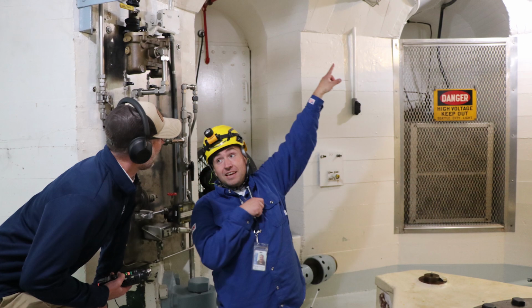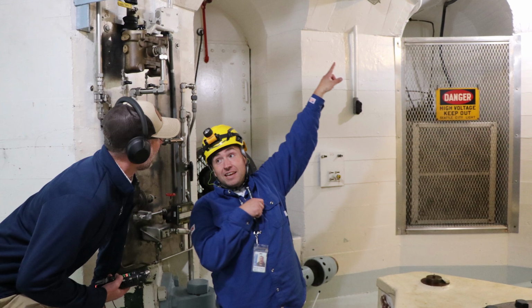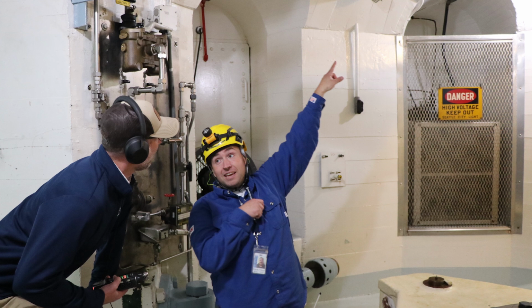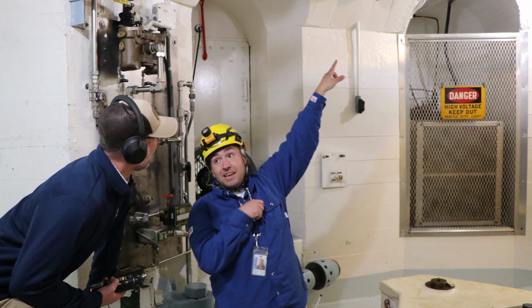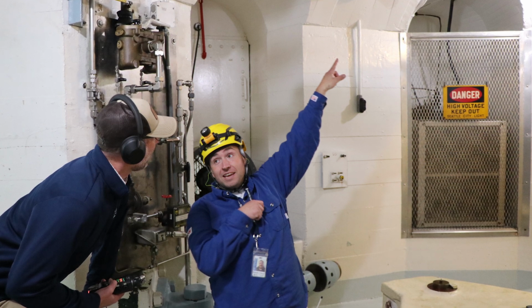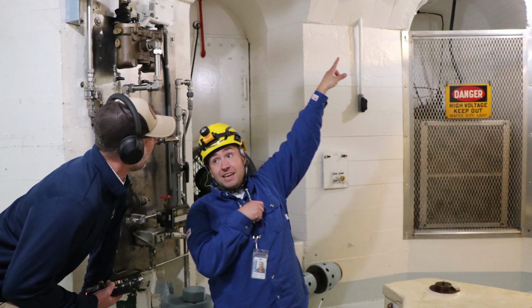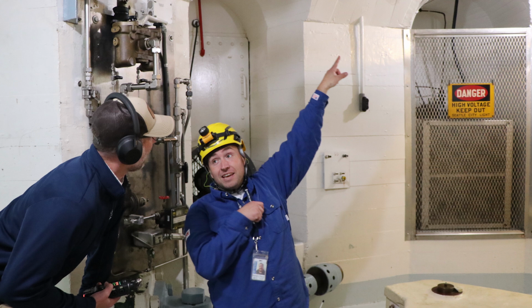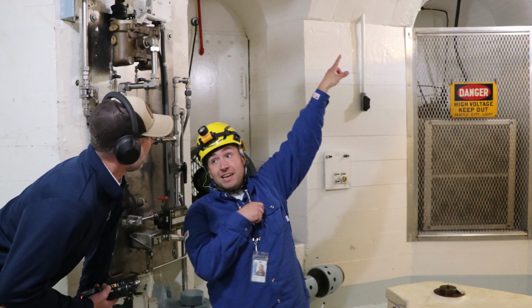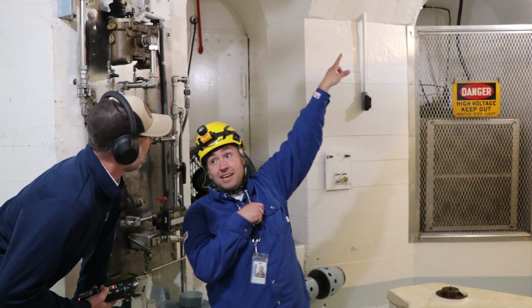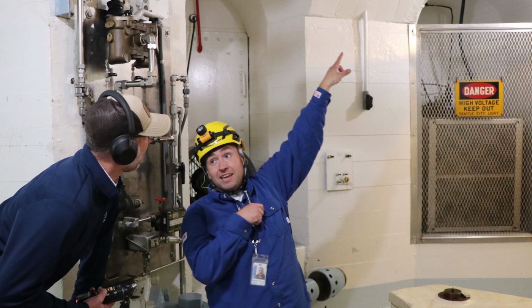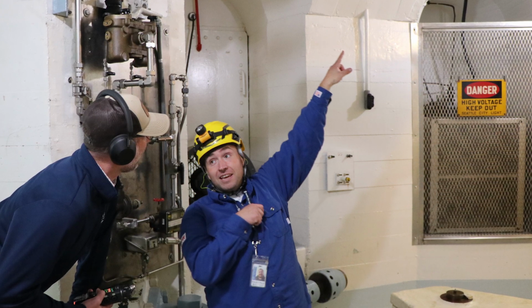It was always talked about here. When something happens, we call it a bump—we got bumped again. The reason it's called a bump is because there's a physical response of the generators to the disturbance, if it's a fault on a transmission line. You've got a million pounds of rotating weight, and when the fault occurs, that million pounds is magnetically directly linked to the grid. Every pole is in phase, or just slightly ahead if you're really into it, of the grid. As soon as the grid changes, even though with a million pounds of rotating weight you're not going to super affect the grid—the grid's super affecting you. So if the magnetism changes, that rotor comes directly into response with that, and you feel it throughout the whole plant.